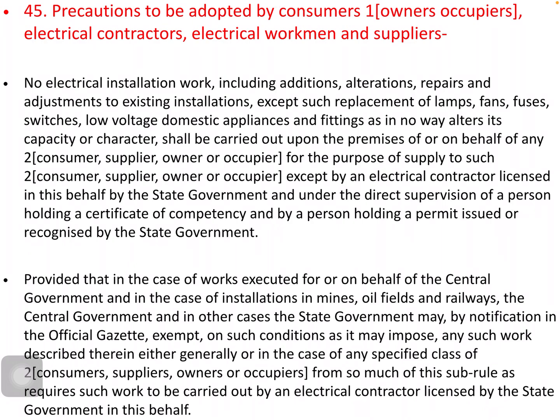Rule 45 talks about the electrical contractor, electrical workman, and the supplier. Here also it is talking about safety. If a workman or a supplier supplies to the consumer, for electrical installation works, any alterations, repairs, or replacement of the existing installation other than the fuses, switches and fans, if he has to alter its capacity or character, then he has to do it under the supervision of a state government licensed person only. Otherwise, it is against the rule.